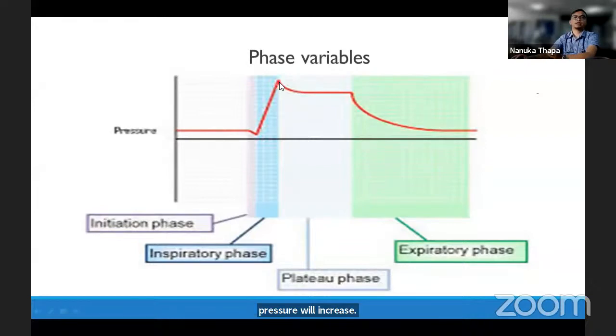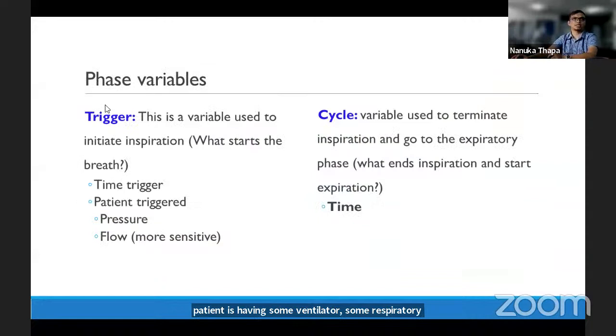After that, there is a plateau phase, in which the pressure is given during this time and will continue. It will not go beyond. After 0.5 seconds, or according to the set inspiratory time, expiration will start. During that time, the pressure given by the ventilator will drop and expiration is allowed, and the same cycle will come. So if you see this dip here, in a patient who is not having obvious spontaneous breathing, you can say that the patient is having some respiratory efforts.